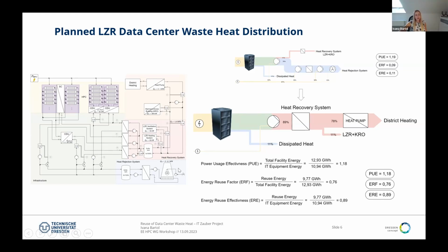Yes, so both of the adjacent buildings would use inlet temperatures from 45 to 50, let's say 47 is our goal, and they use low temperature heating and ventilation. But district heating would also need much higher temperatures, around 90 degrees Celsius. This is exactly why we would need to implement a heat pump, to bring the temperature from 47 to 90.